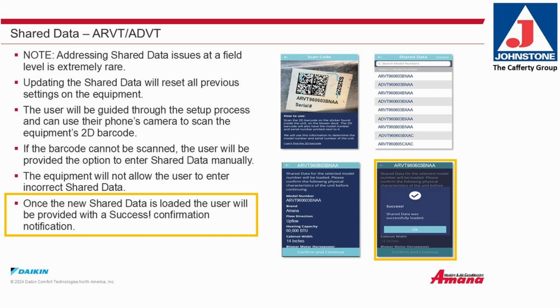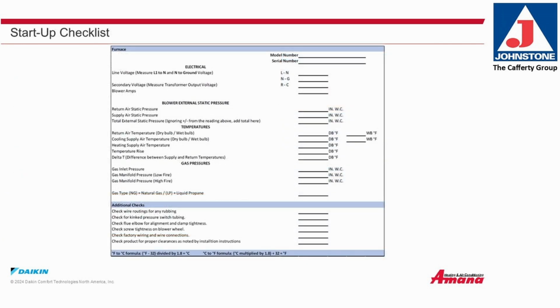Here is a startup checklist for a furnace. Please fill in all the information. Here's where you would list the model number and the serial number. In the electrical section, we have line voltage measuring L1 to neutral and neutral to ground. Secondary voltage measuring transformer output voltage, and then reading the blower amps.